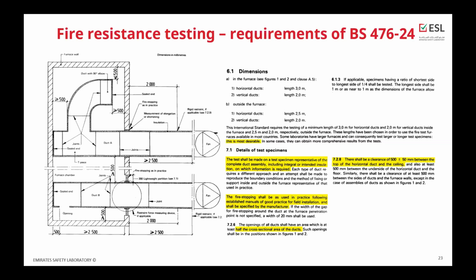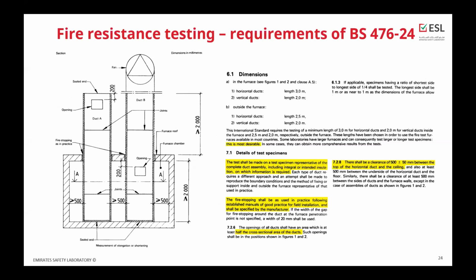Duct B has the opening, which is located inside the furnace, half a meter from the end of the duct. And as you can see in the highlighted information, one of these is the fire stopping, which should be as in practice during the installation. We are talking here about the minimum length of the duct, so we can extend. And the BS is telling that if we can test a longer duct, this is the most desirable situation. For vertical ducts, it's quite a similar scenario. Besides that, duct A can have no branch.